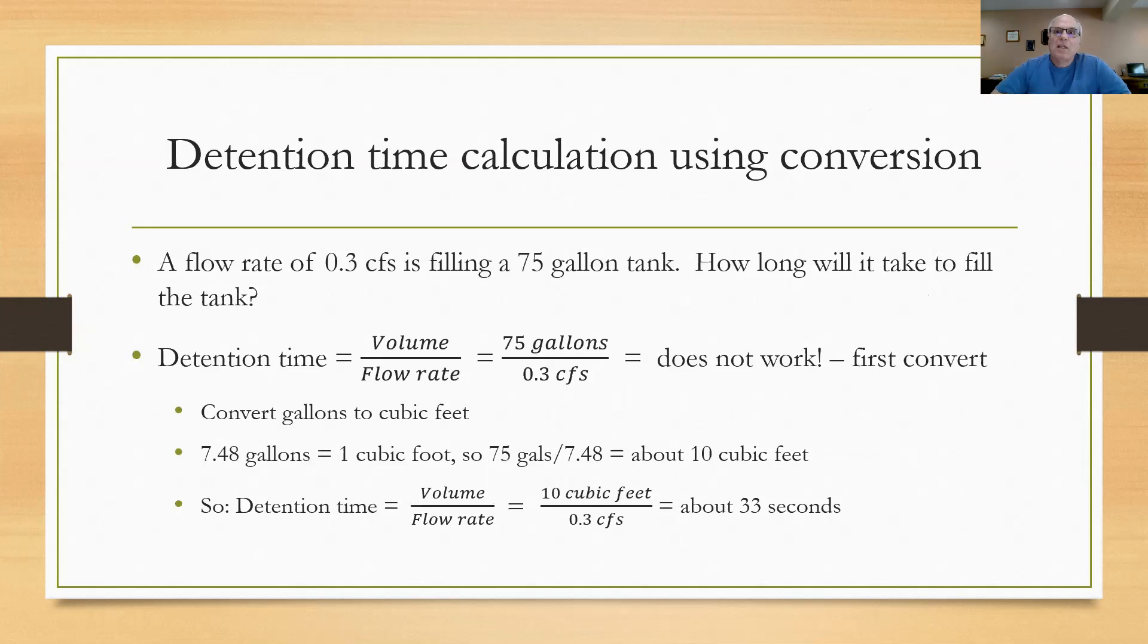Here's a detention time calculation using conversions. They tell you a flow rate of 0.3 cubic feet per second and you're filling a 75 gallon tank. How long is it going to take to fill the tank? Well, we set up our detention time volume divided by the flow rate. So we put 75 gallons, which is the volume in the numerator. In the denominator, we divide by 0.3 cubic feet per second. And that is not going to work. You can't divide gallons by cubic feet per second. So you have to convert something. And what I've chosen to do here is to convert the gallons to cubic feet.